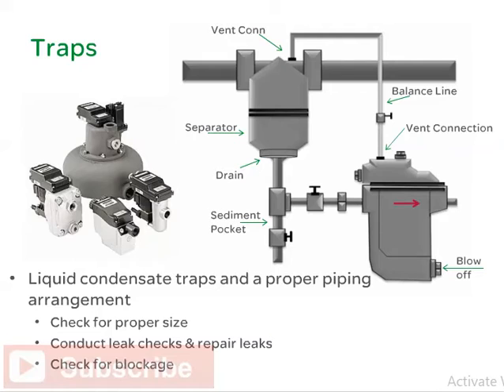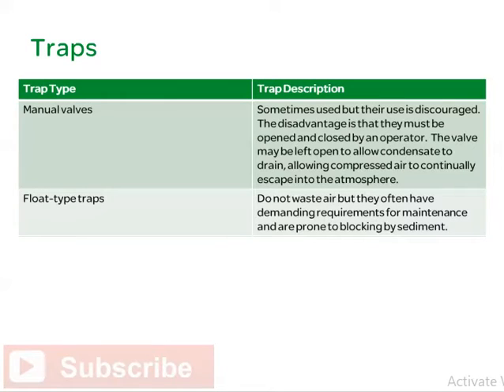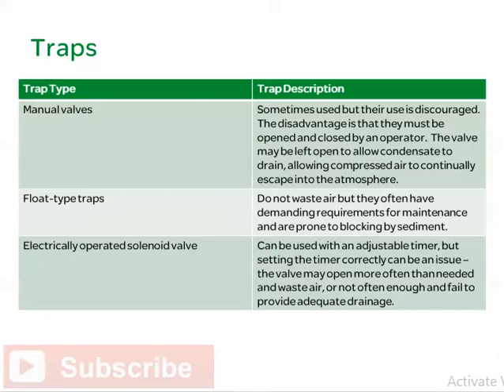Check for blockage. Manual valves are sometimes used, but their use is discouraged. The disadvantage is that they must be opened and closed by an operator. The valve may be left open to allow condensate to drain, allowing compressed air to continually escape into the atmosphere. Float-type traps do not waste air, but they often have demanding requirements for maintenance and are prone to blocking by sediment. An electrically operated solenoid valve can be used with an adjustable timer, but setting the timer correctly can be an issue. The valve may open more often than needed and waste air, or not enough, and fail to provide adequate drainage.